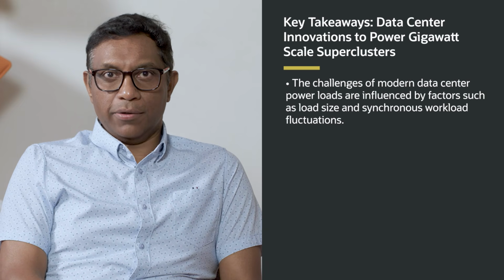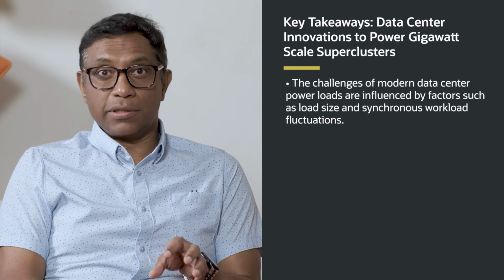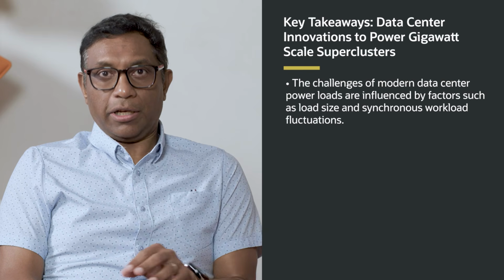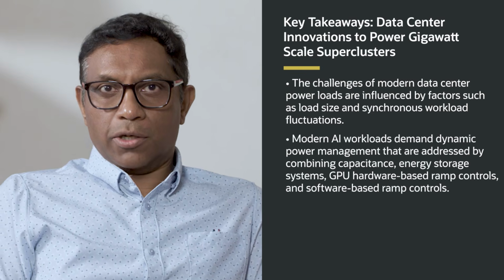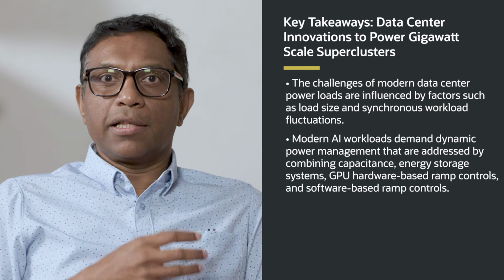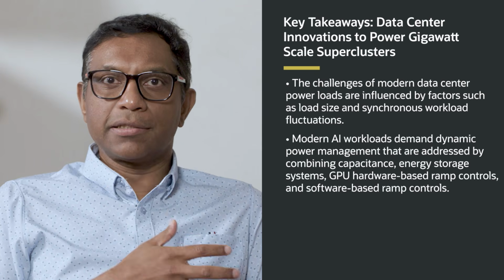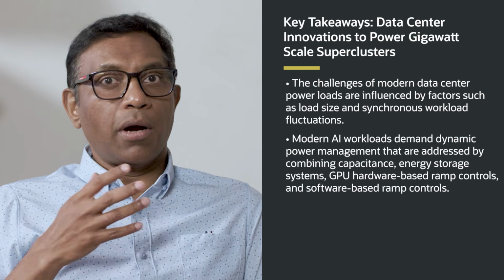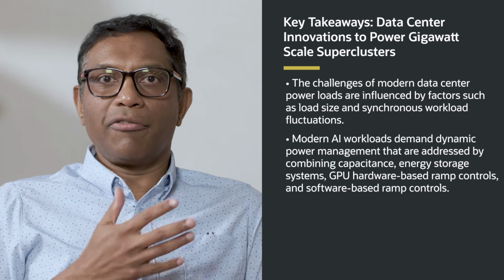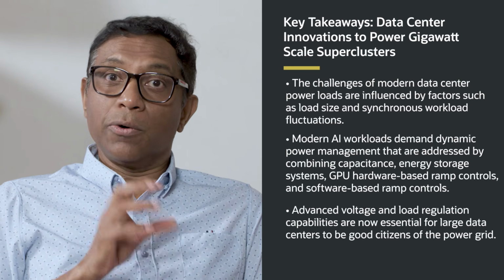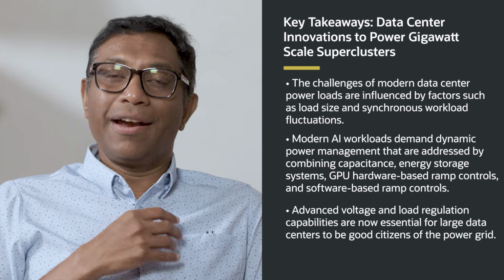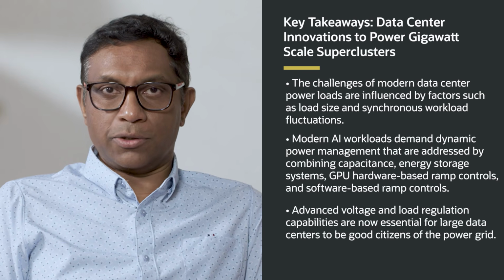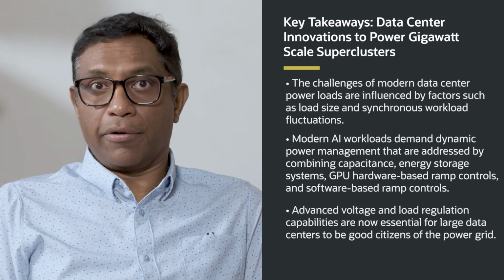Here are some of the key takeaways from our conversation on OCI data center innovations. The challenges of modern data center power loads are influenced by factors such as load size and synchronous workload fluctuations. Modern AI workloads demand dynamic power management that is addressed by a combination of capacitance, energy storage systems, GPU hardware-based ramp controls, and software-based ramp controls. Advanced voltage and load regulation capabilities are essential for large data center campuses going forward in order to be good citizens of the power grid.